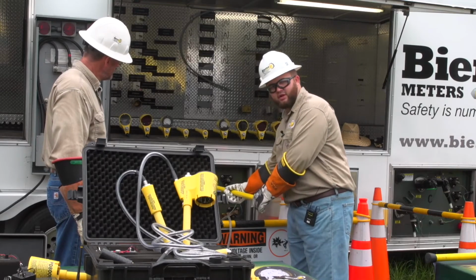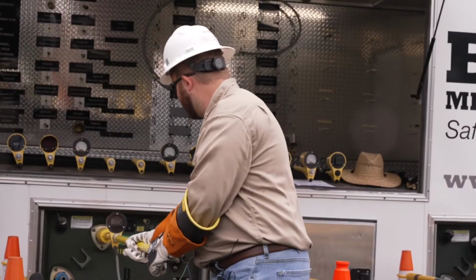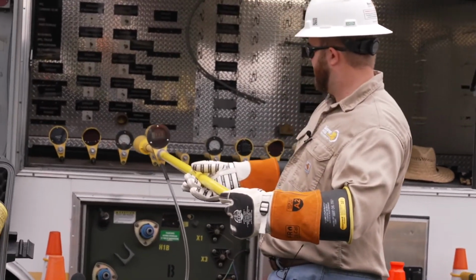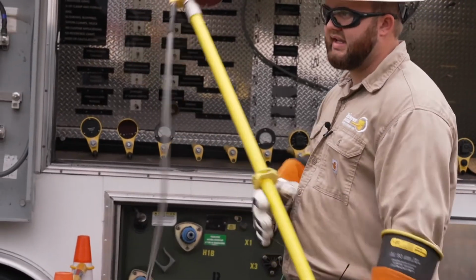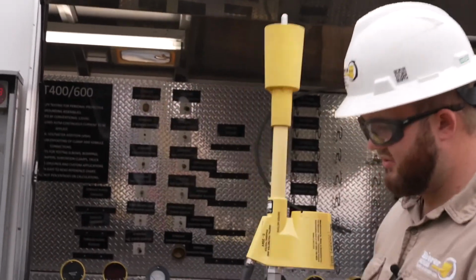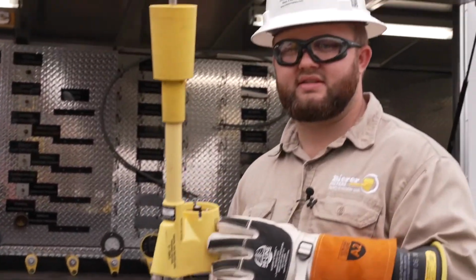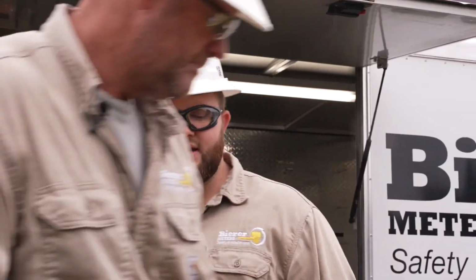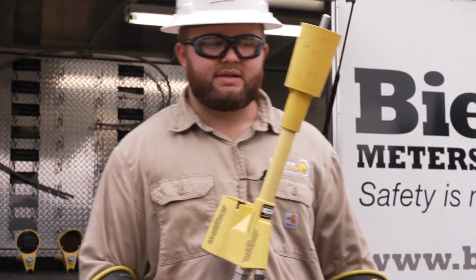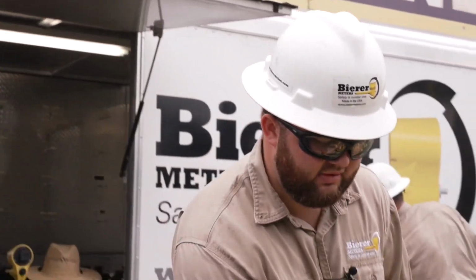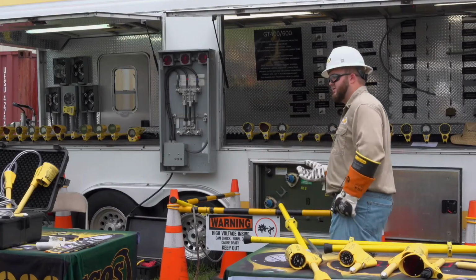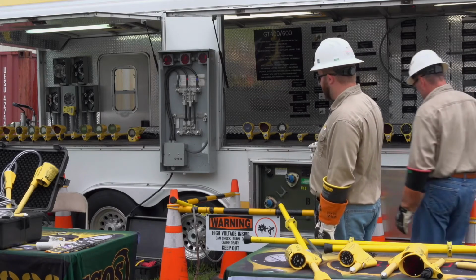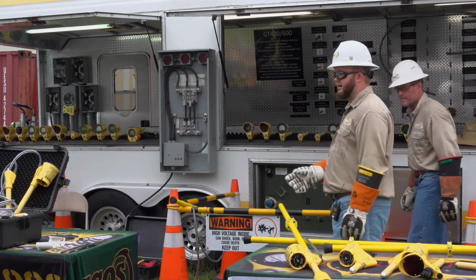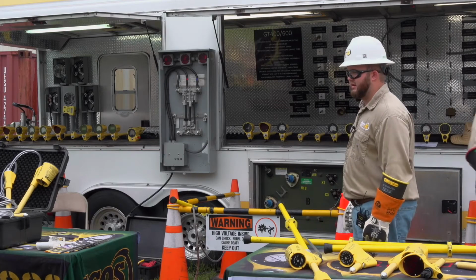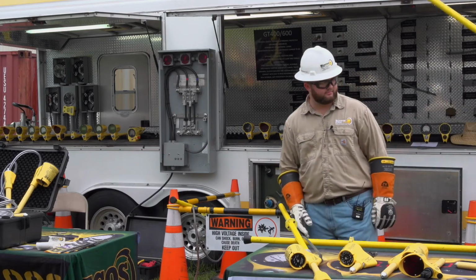So here, if you watch close, you'll see it drain here kind of quick. It takes a second to drain that potential between the two, just because of the resistance in the probe. There's nothing wrong with the device, but that's the same thing you want to do when high potting. Usually the rule of thumb with high potting is however long it took to charge the cable, that's how long you want to take your second probe to ground to discharge that capacitance you built up.